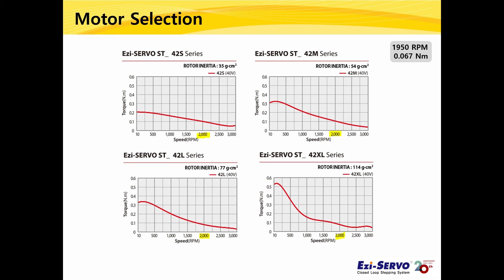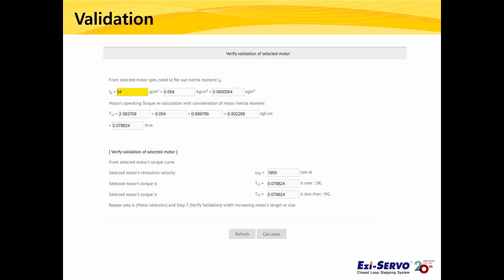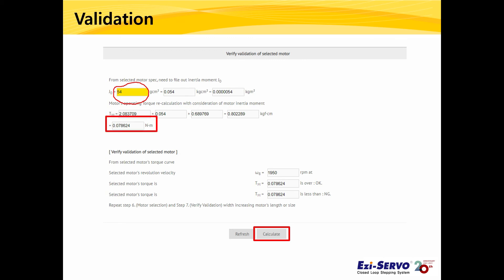Therefore, we can recommend a 42M motor that can produce the largest torque at 2000 rpm — approximately 0.1 Nm, with a moment of inertia of 54 g·cm². We need to verify the motor by entering the inertia value and recalculating the required torque with motor inertia included. Enter 54 as the moment of inertia of the 42M motor in the yellow box and click Calculate. The required torque is then calculated as 0.078 Nm. Since the 42M motor can produce 0.1 Nm at 2000 rpm, 0.078 Nm is within an acceptable range.